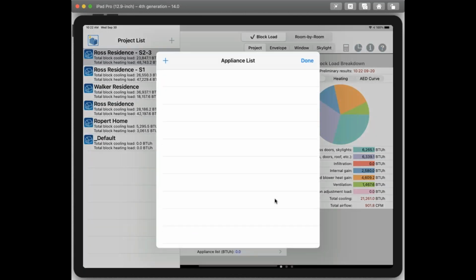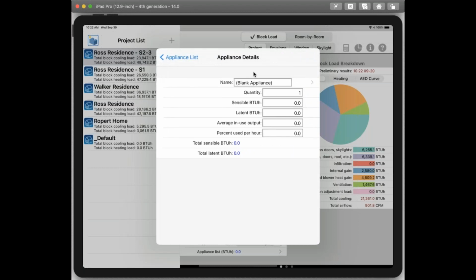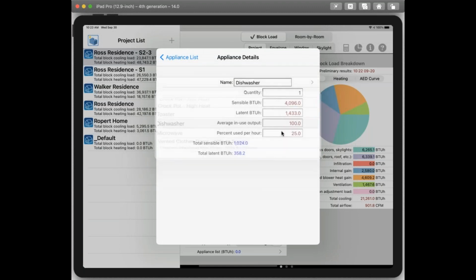And what custom allows you to do is add a customized list of appliances you have throughout your whole home. So here's a list that comes from the ACCA Manual J8 handbook. Let's say dishwasher, and I have one, and this is the sensible and latent loads that the dishwasher contributes to my home. Now, it doesn't contribute 100% of the time. It only contributes 25% of the time, say. So then it multiplies these numbers together and provides us the average sensible and latent load for a dishwasher.